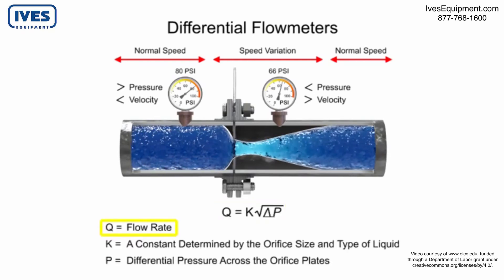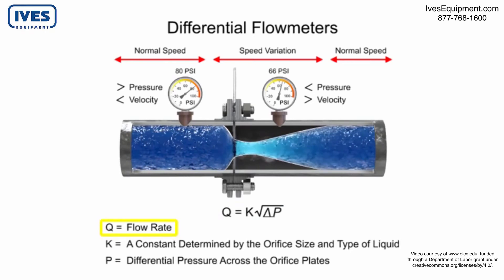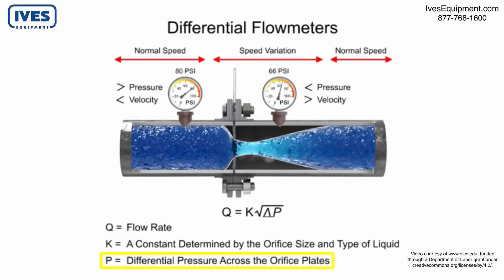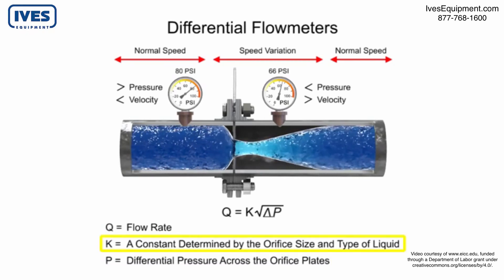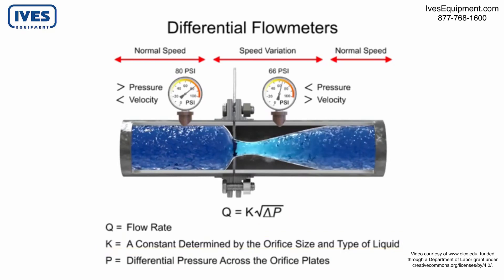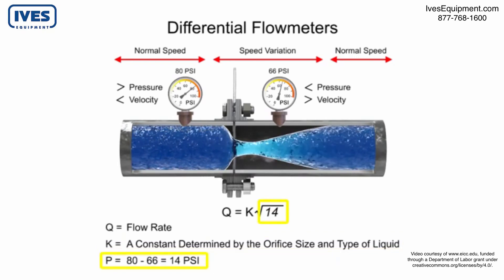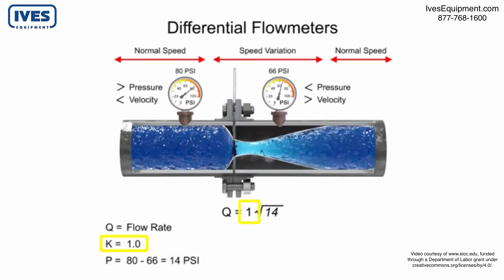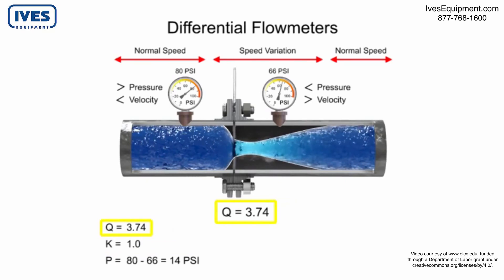The flow rate, q, of a fluid through an orifice plate increases in proportion to the square root of the pressure difference on each side multiplied by the k factor. For example, if the differential pressure increases by 14 psi with a k factor of 1, the flow rate is increased by 3.74.